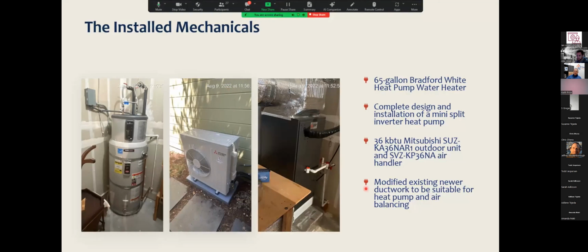The house had newer ductwork. Originally, we were going to put a system up in the attic, a really small 18,000 downstairs and a 12,000 in the attic. Well, they didn't want to do that once they figured out we had to put line set up the side of the house, which is really a beautiful home. So we just ended up doing a couple of tricks to the ductwork to balance things out, and put this 36,000 in. This particular 36,000 BTU unit can slow down to about 11,000, so that's pretty good.